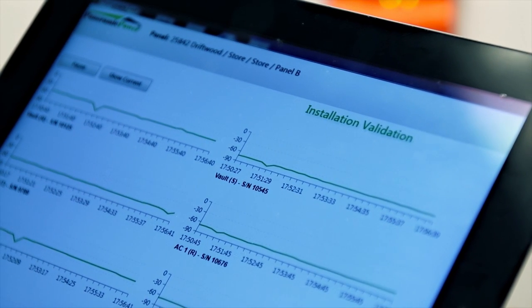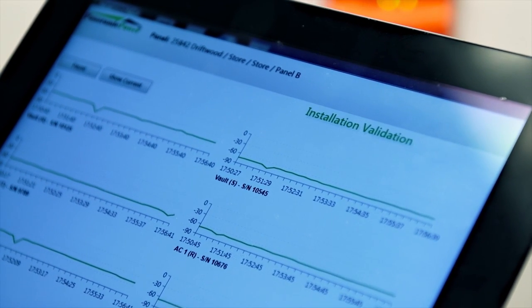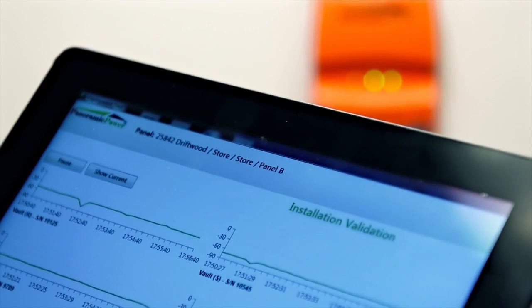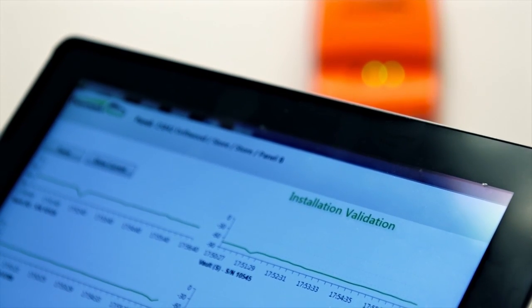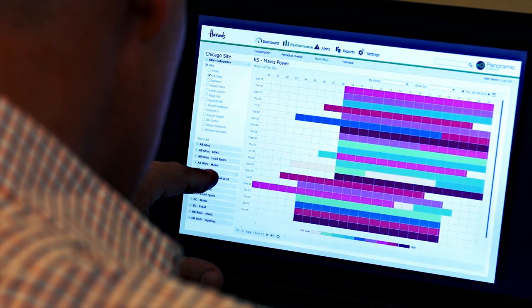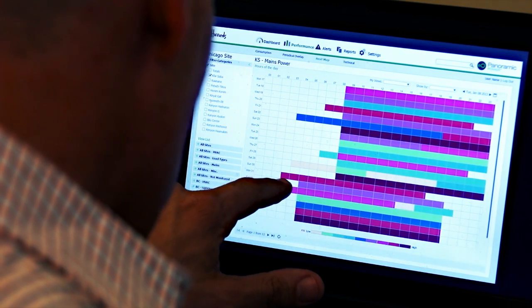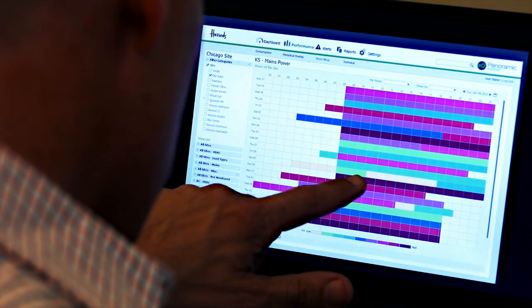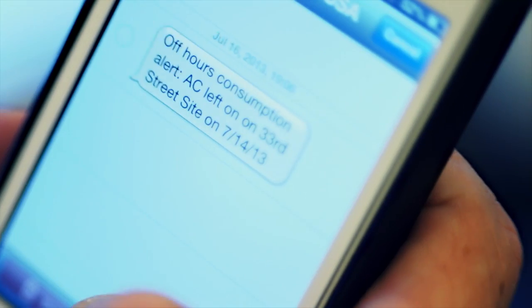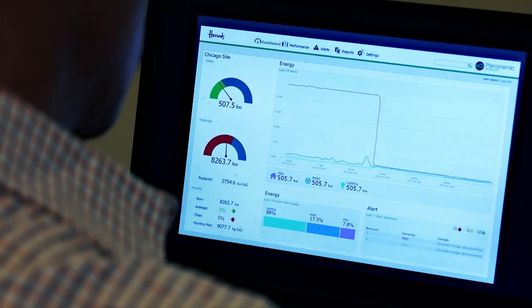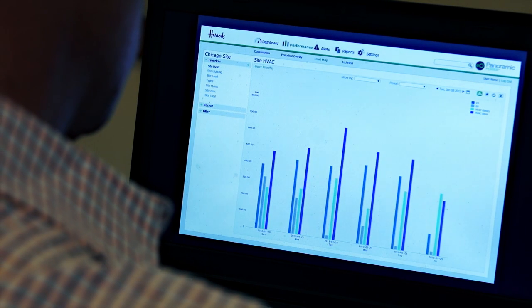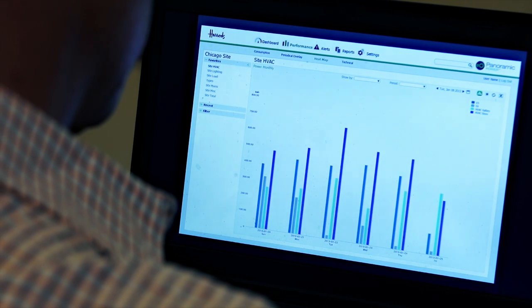Once the bridge is connected and the panel boards are closed, reception from all sensors is verified. The RX LED on the bridge will blink when a sensor message is received. You can then activate the system dashboard and start receiving invaluable energy data. Set up energy alerts, reports, and explore the data using our cloud-based analytic tools.